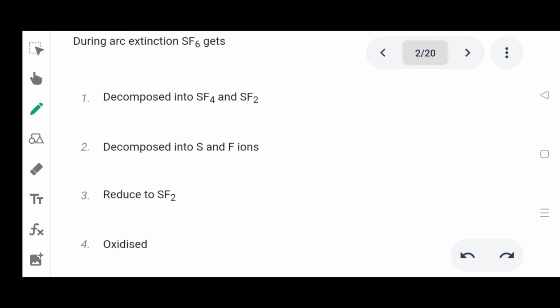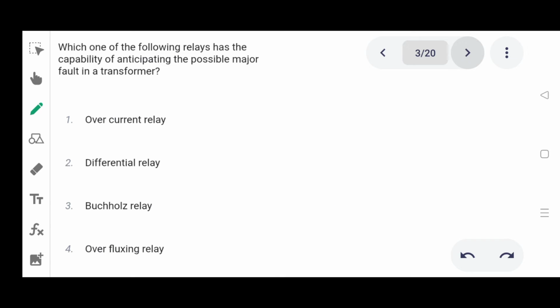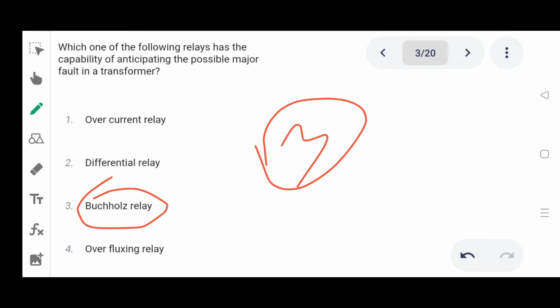During arc extinction, SF6 gets: option 1, decomposed into SF4 and SF2; 2, decomposed into S and F ions; 3, reduced to SF2; 4, oxidized. Correct answer is decomposed into SF4 and SF2, option 1. Next one. Which one of the following relays has the capability of anticipating the possible major fault in a transformer? Option 1, overcurrent relay; 2, differential relay; 3, Buchholz relay; 4, overfluxing relay. Correct answer is Buchholz relay.